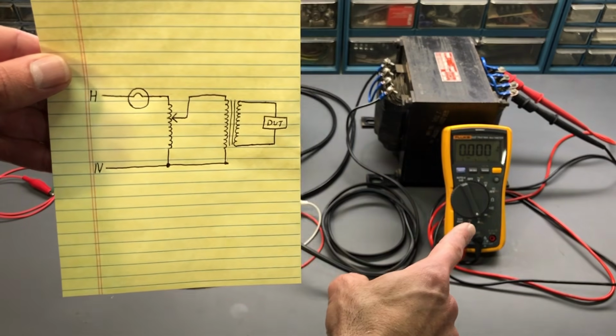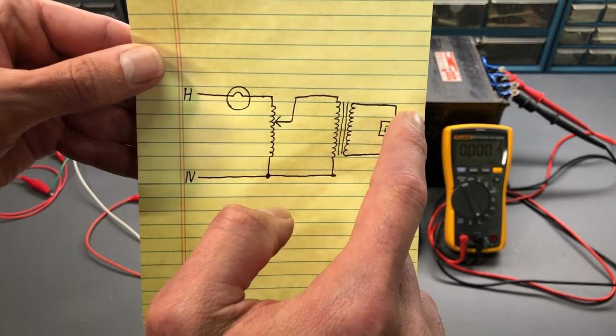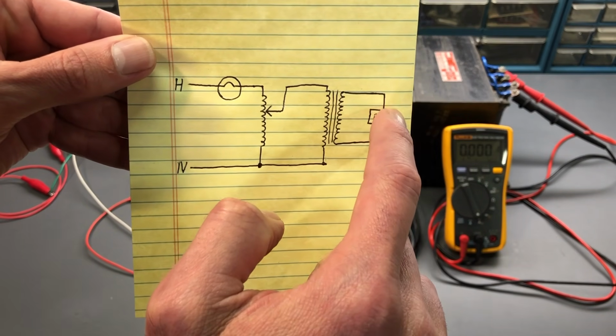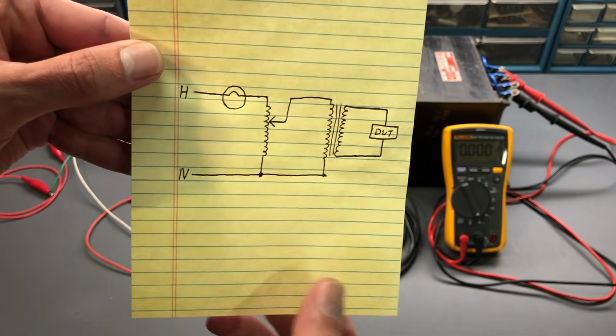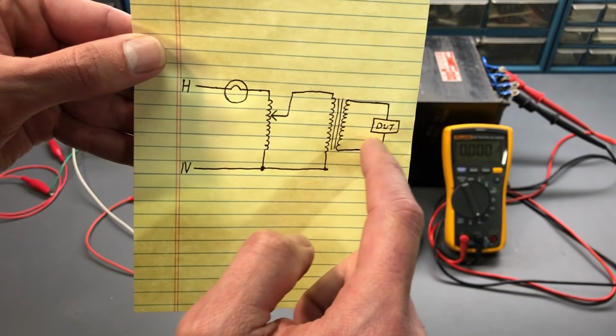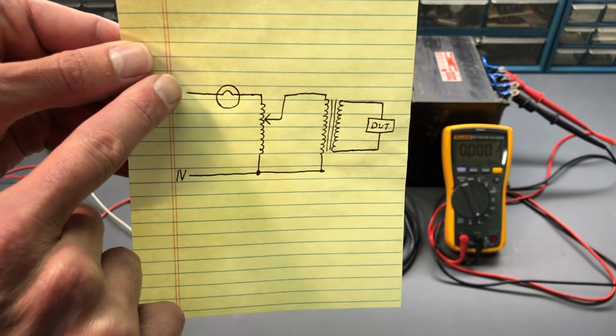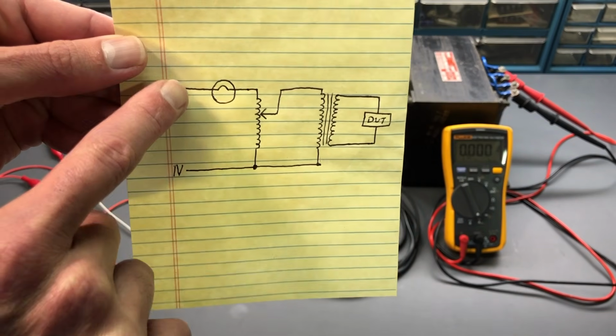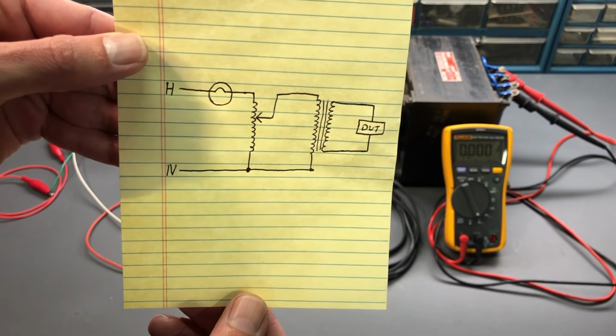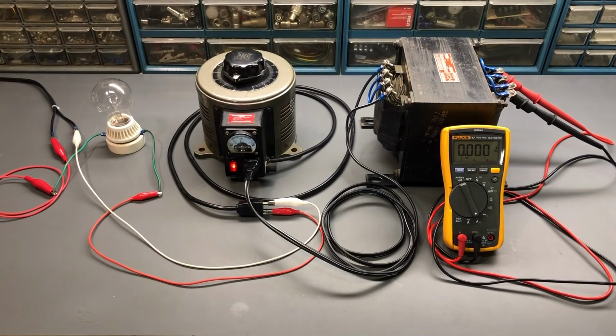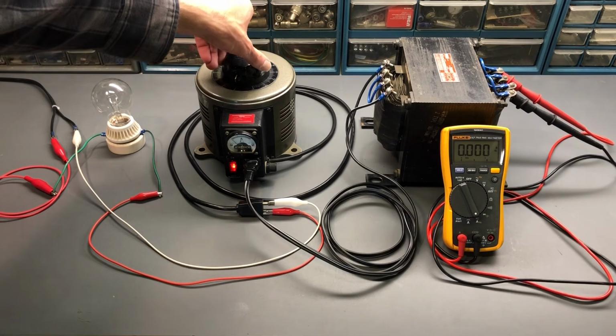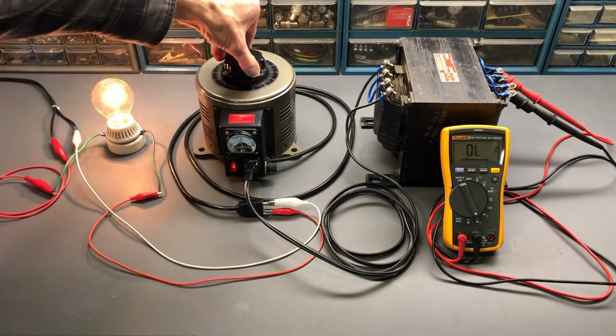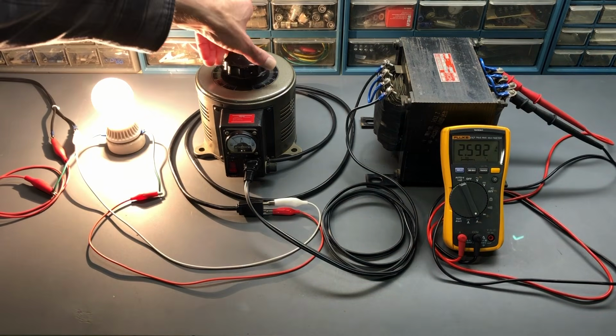So on the secondary side of the isolation transformer, over there, we have the device under test, DUT, which is the Fluke 117 digital multimeter, and it's in the current position, so it's acting like a direct short across these windings right here. So we're going to find out what is the current that can flow through these windings when we put full 120 volt AC on the input over here. And again, if you're following along, you do so at your own risk. So just be cautious and take care. All right, so I'll increase the voltage. And we can see the bulb comes up to full brilliance.